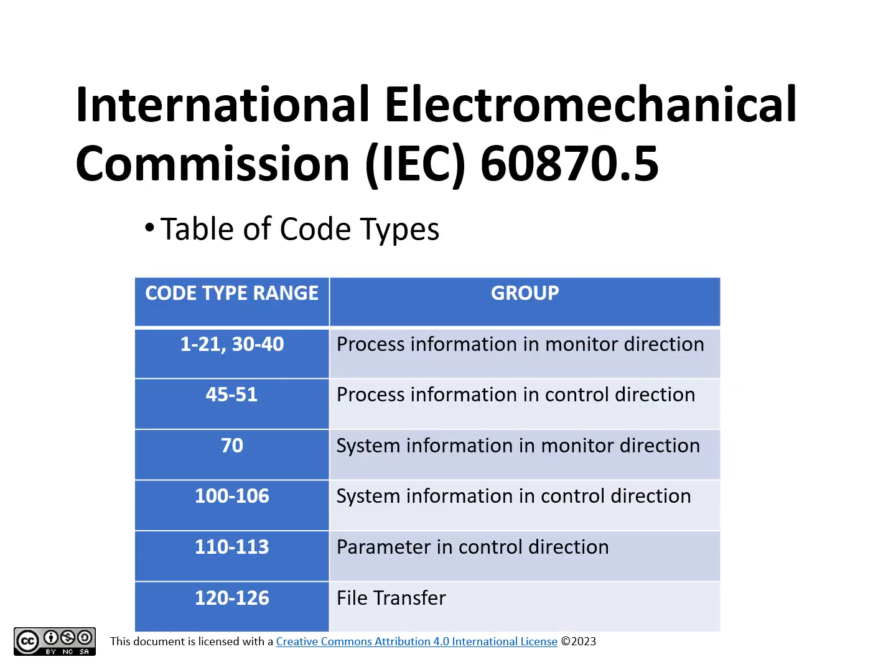The 8-bit wide code types shown in the table below identify some of the 58 groups that are currently defined. Furthermore, information code references defined in IEC 60870-5-104 are provided in the ASDU. For instance, code type number 9 has reference code M_ME_NA_1, indicating measured value, normalized value.